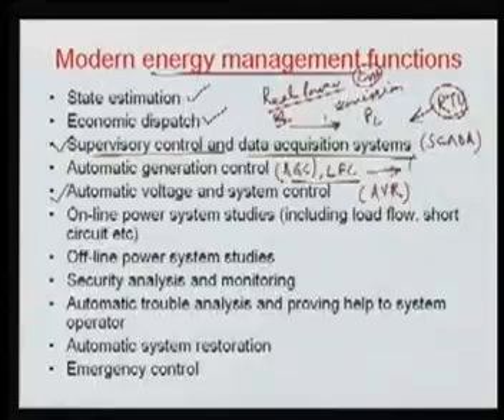In the AGC, as I said, we control the frequency of the system, and this frequency is global in nature, meaning the frequency of the whole system is the same. However, the voltage at the individual node, the individual point, is different. So automatic voltage control means we have to control the excitation of the generators so that we can achieve our system voltage profile, and thereby we can generate the reactive power.